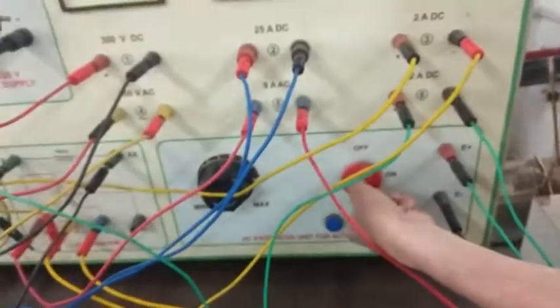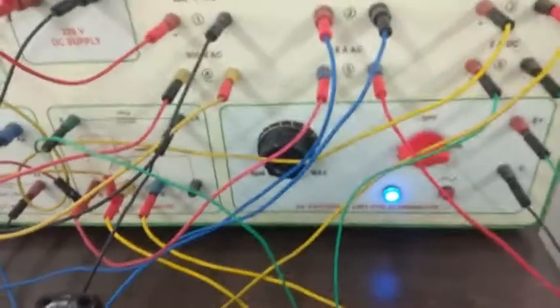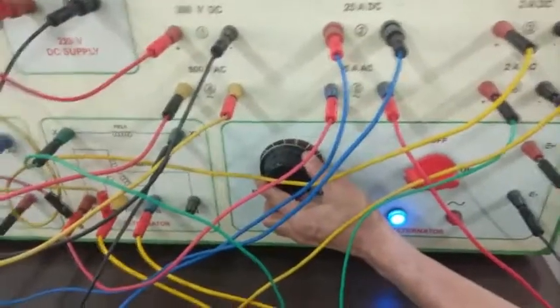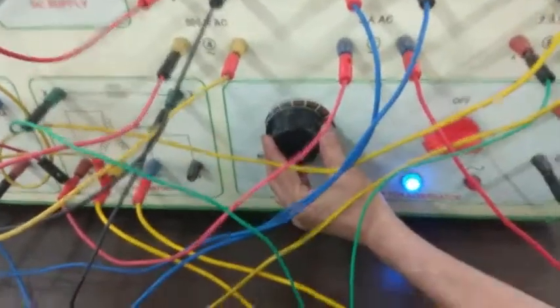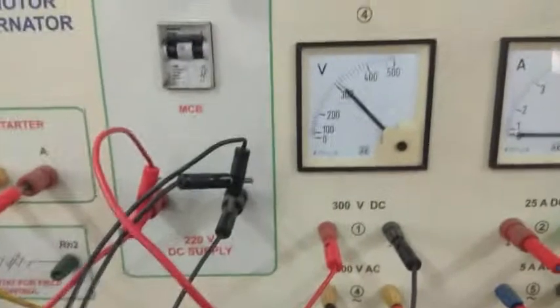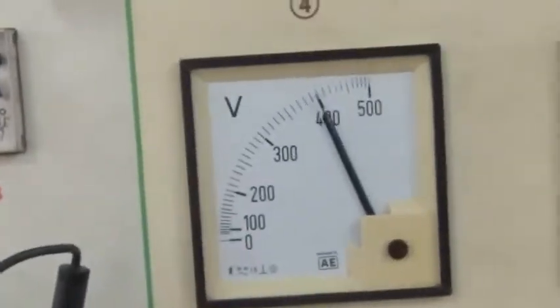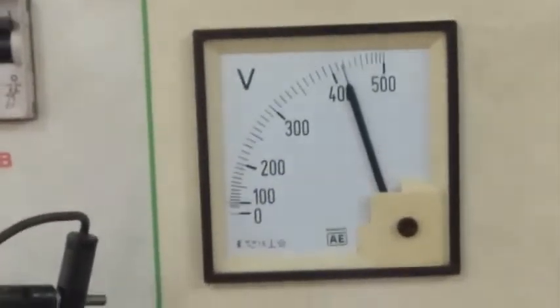Now we will switch on the alternator switch. Yes, we will switch on the alternator switch. Okay, and we will vary the excitation up to 415 volt. You can see we are varying the excitation up to 415 volt. 400. Yes, okay. Reduce it a little, enough, enough.